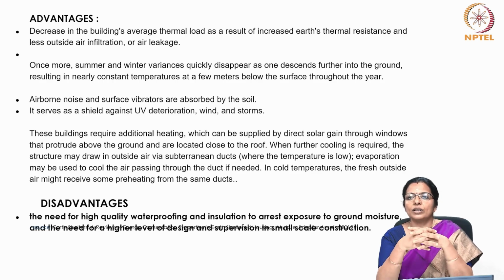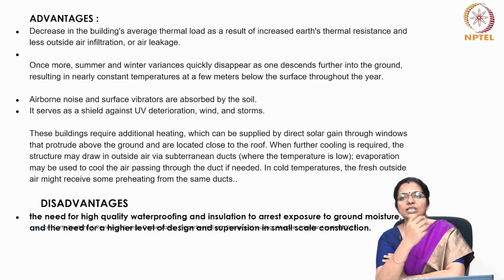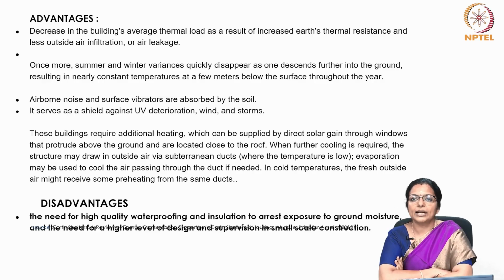When further cooling is required, the structure may draw in outside air through subterranean ducts where the temperature is low. Evaporation may be used to cool the air passing through the duct if needed. In cold temperatures, the fresh outside air might receive some preheating from the same ducts.